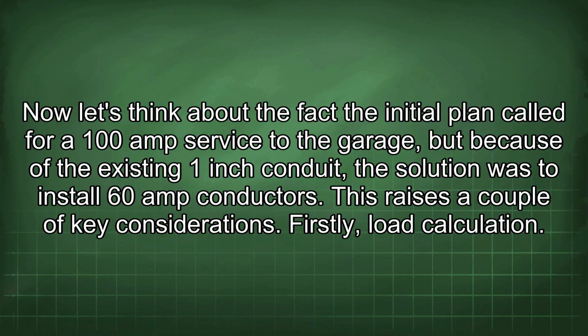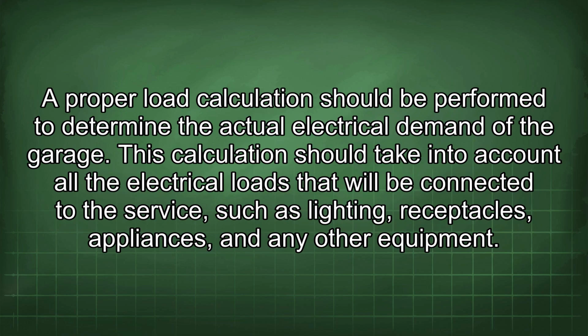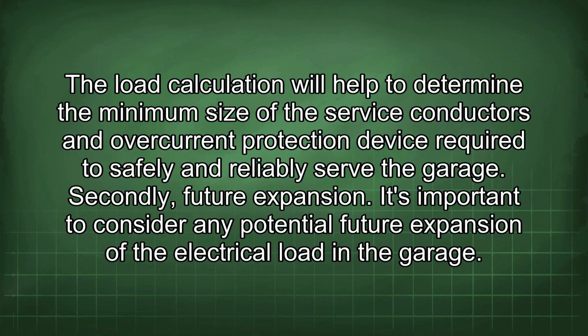Firstly, load calculation. A proper load calculation should be performed to determine the actual electrical demand of the garage. This calculation should take into account all the electrical loads that will be connected to the service, such as lighting, receptacles, appliances, and any other equipment. The load calculation will help to determine the minimum size of the service conductors and overcurrent protection device required to safely and reliably serve the garage.